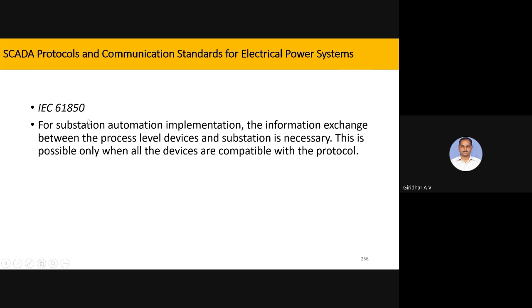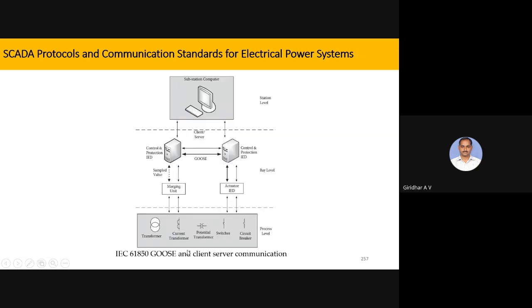So IEC 61850, typically in modern digital substations, they are trying to use such standards. IEC 61850, they are implementing. So the whole substation they are making digital. In some places they are implementing it where the whole substation is digital. So with these protocols, they are using IEC standards. All these things will be converted into digital and passed on to the master stations.